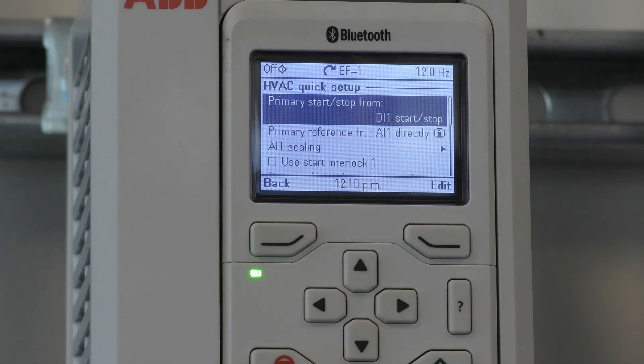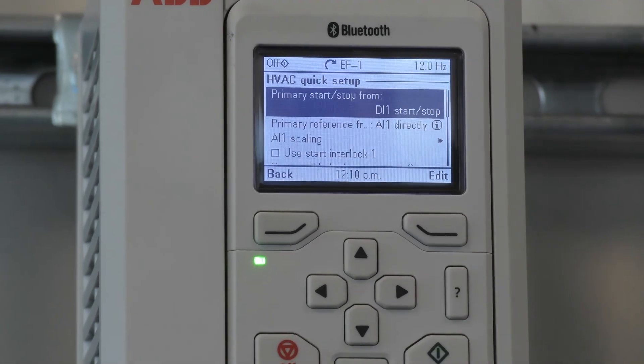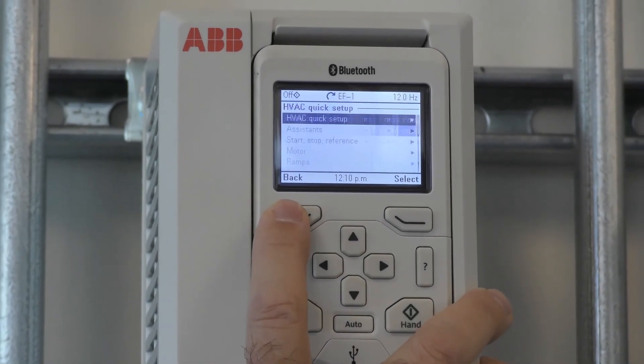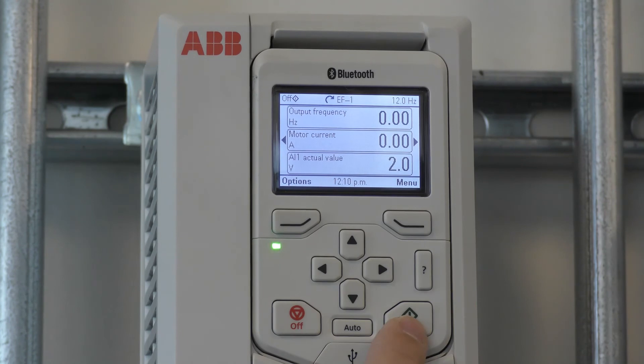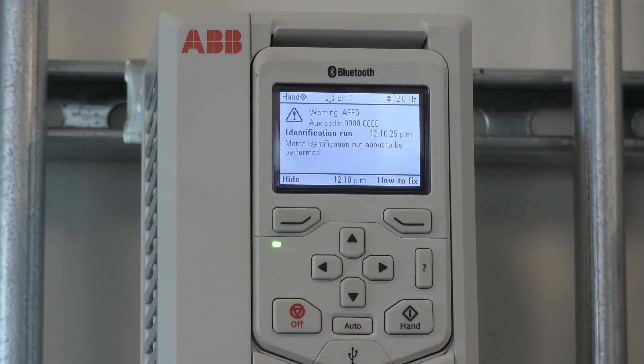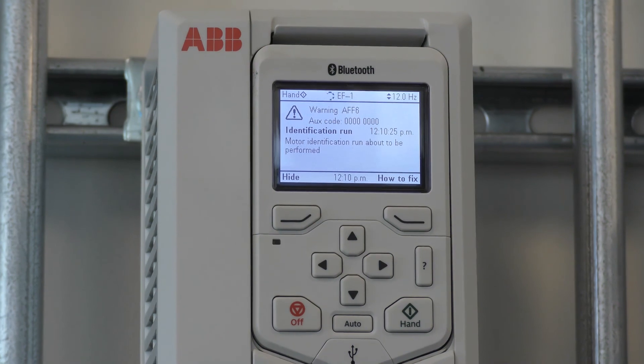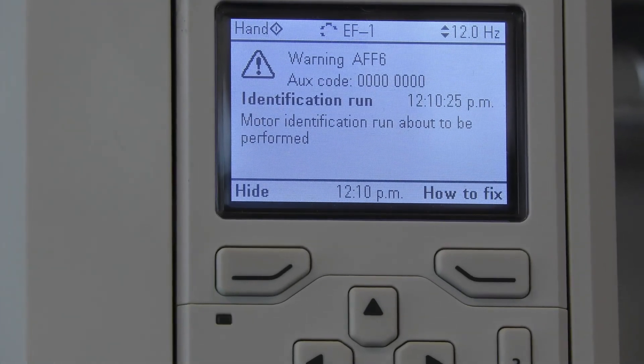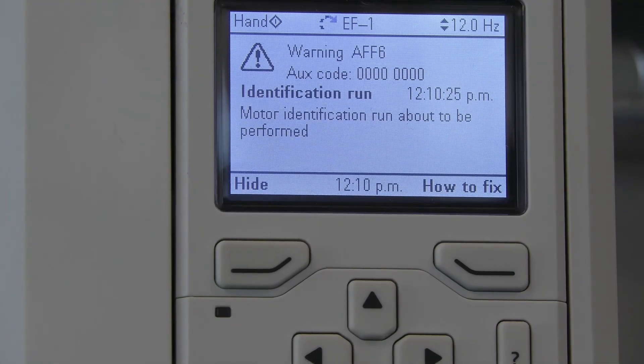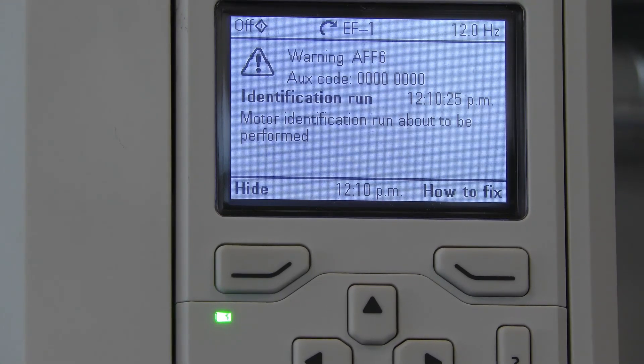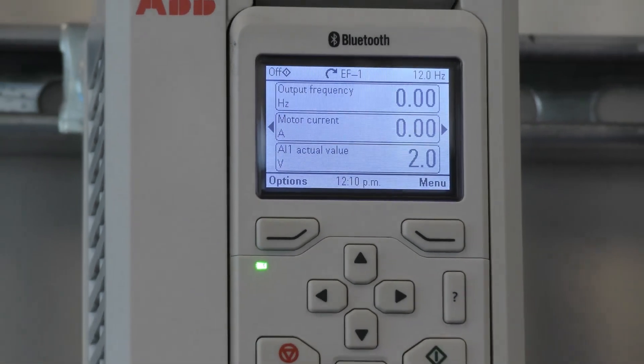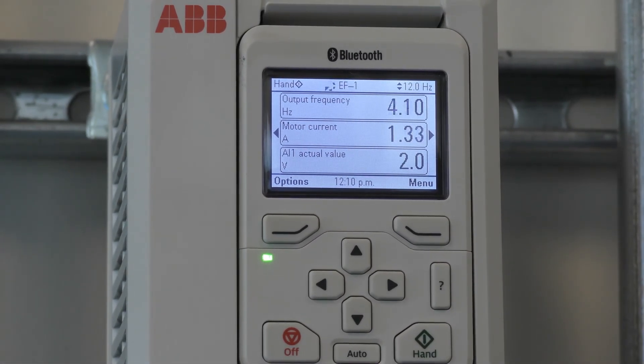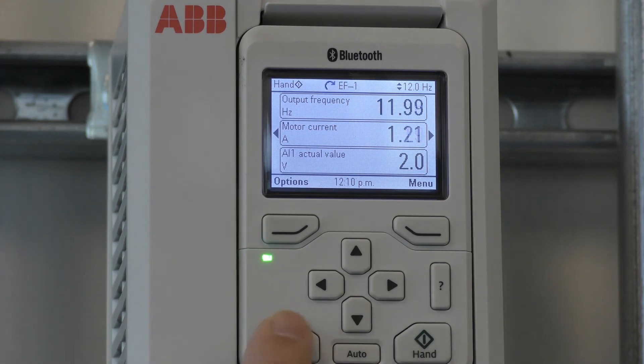Now we are back to where we began, and we can start the drive in hand mode to initiate the identification run. Go back to the main screen and press the Hand button. The drive is performing an identification run, which gets the characteristics of the motor it is connected to. Once this is done, you'll have to press Hand again to check rotation. If you check rotation and find that it is going the wrong way, press Off.